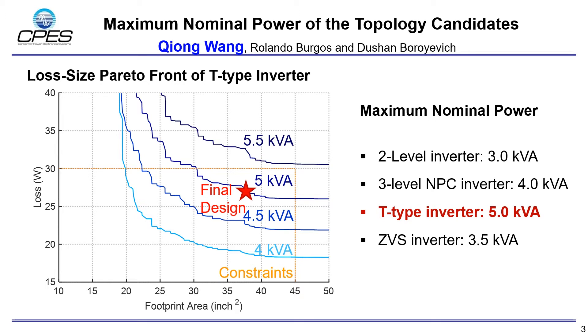To find out the proper topology as well as optimal design, we have explored the loss and size Pareto fronts, which demonstrates the trade-off between loss and size of all topologies on their various power levels. The Pareto fronts shown here belong to the T-type inverter. Considering the loss and size limit, it shows that the T-type inverter can achieve a 5 kVA maximum nominal power, which is higher than the other candidates. Thus, the T-type inverter is selected.